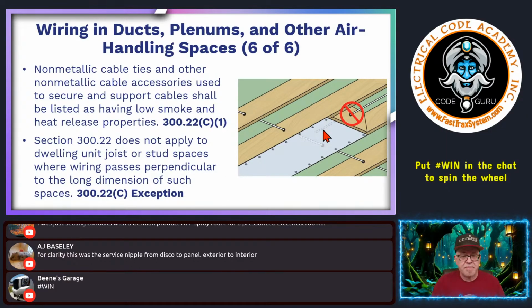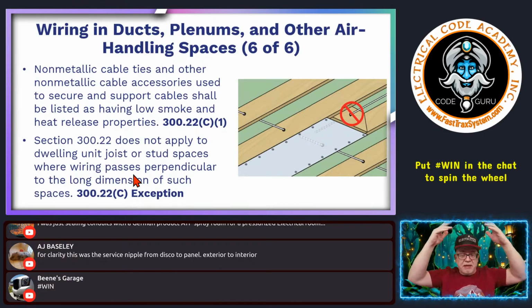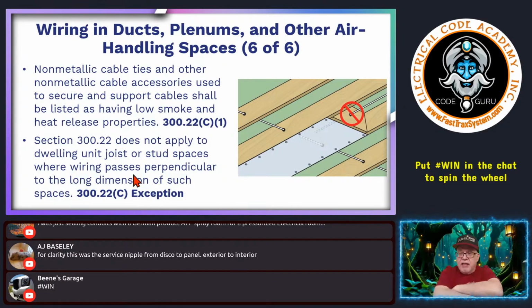I have seen many times where the electrician has run it up the framing member, and there's a return down here, and the electrician has wire in there and didn't think about the fact that the duct folks are going to be using that cavity. It's the chicken or the egg, who did it first. But if the inspector sees that it's going to be used as a return, they're probably going to reject you unless it's running perpendicular with the cavity. So just like we see here, this way is not going to work, this way is perfectly okay, and it happens all the time in dwelling applications.